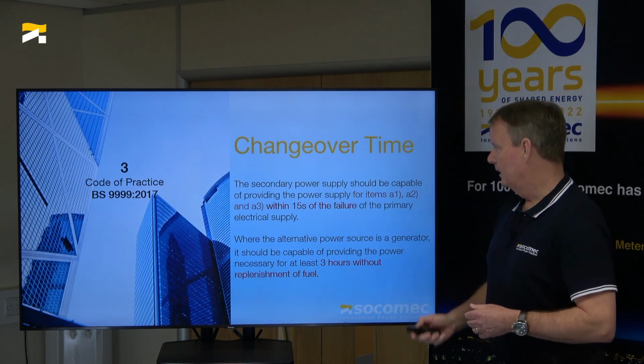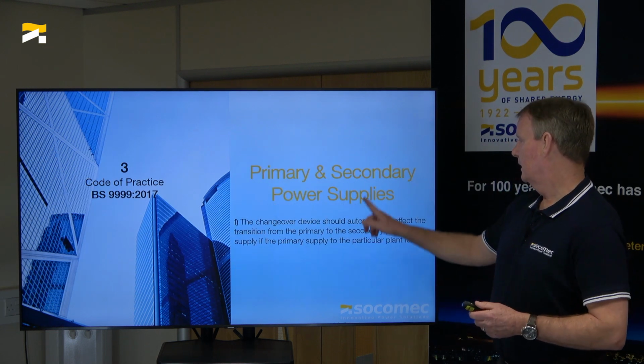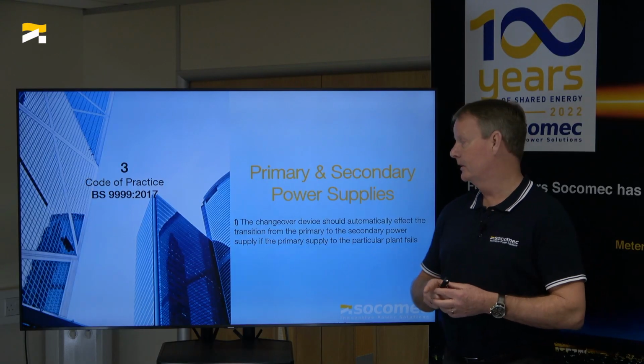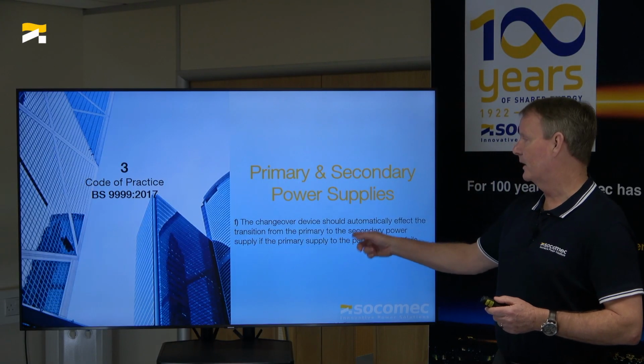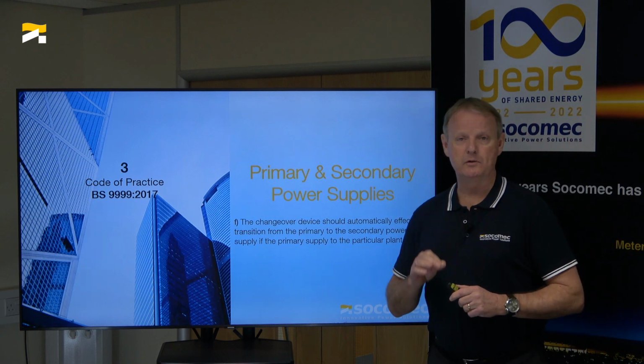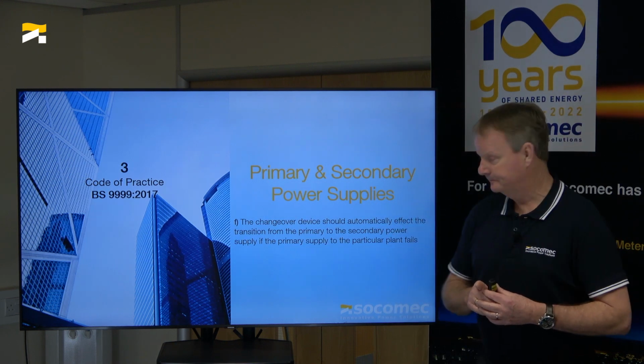One of the other things it says, particular in section F, is that it should automatically change over from primary to secondary power supply. What that's saying is you can't use a manual changeover switch. We sell manual changeover switches at Socomec, like many others do, but in this case, because it's firefighting and fire safety, you cannot use a manual transfer switch.